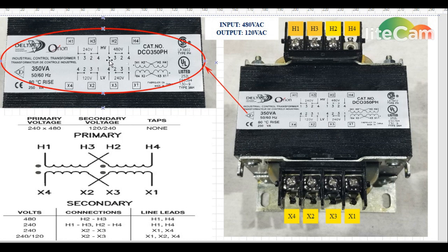Now before we go into the wiring part, let me tell you what the primary and the secondary coil on the transformer are. So these four terminals H1, H3, H2, H4 represent our primary coil. We call it the primary coil because we will be feeding our main voltage to the primary coil. For this video I'm using 480 as the main incoming voltage to my transformer, and we will feed this 480 voltage on the primary side of the transformer.